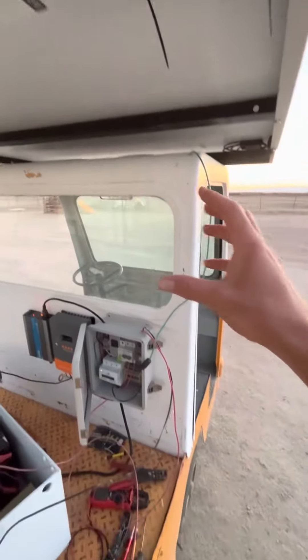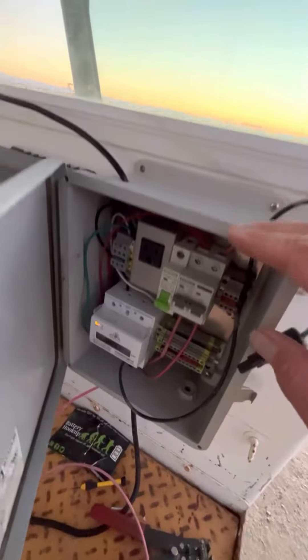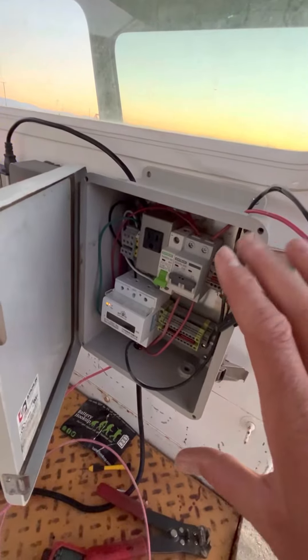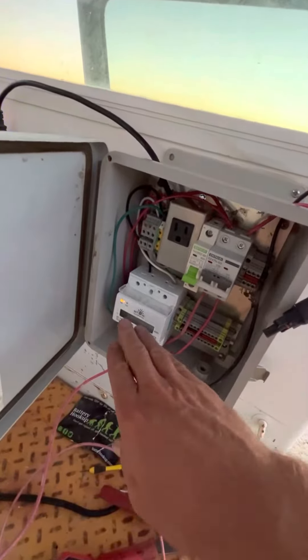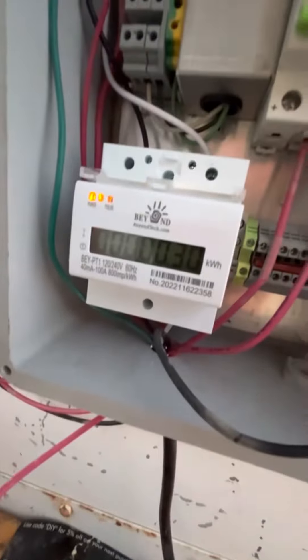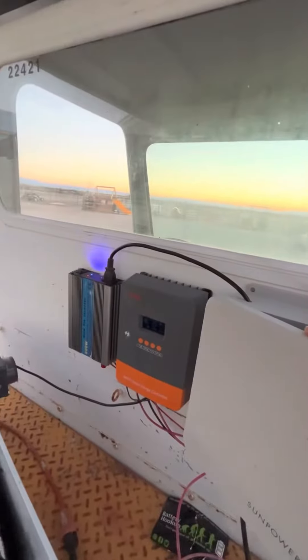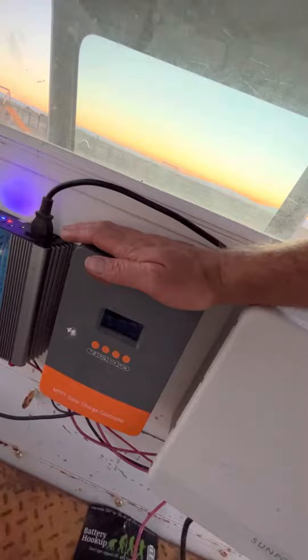Right now I'm just re-making it look a little prettier. They all come down into our combiner box that just has various different switches and DIN rail connections. Then we got a meter for metering our AC so we can see what's going on and how much money we're saving while we run the grid-tie inverter. Solar comes down through the breaker, comes down to our charge controller.